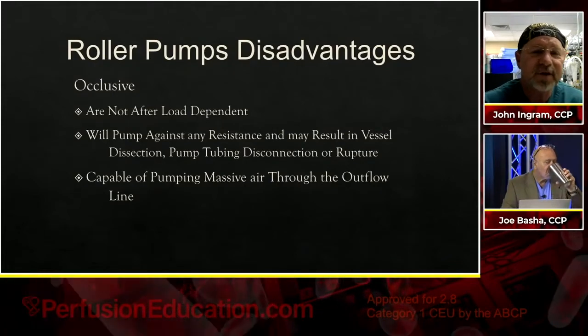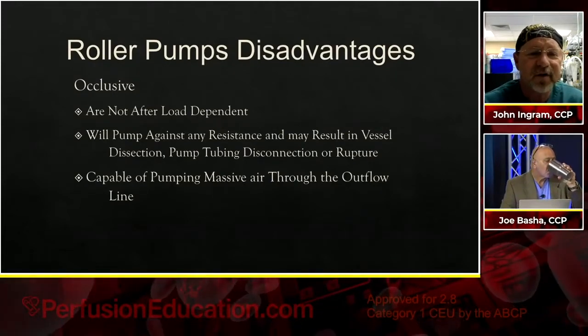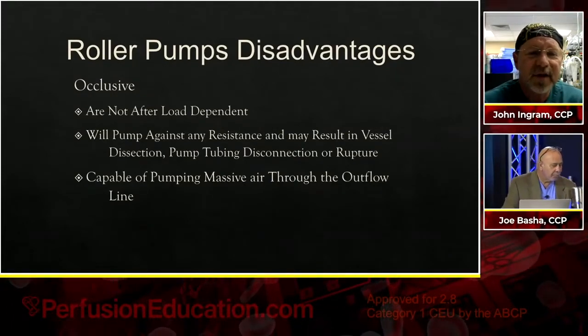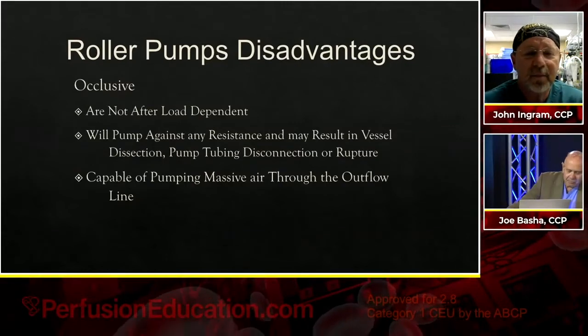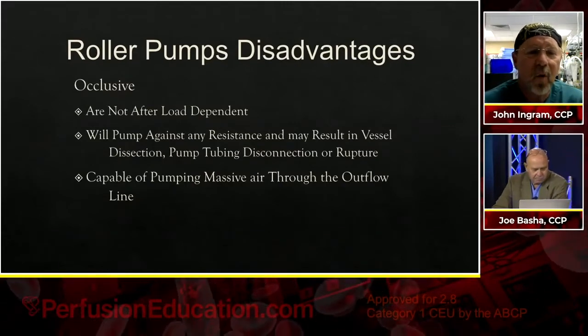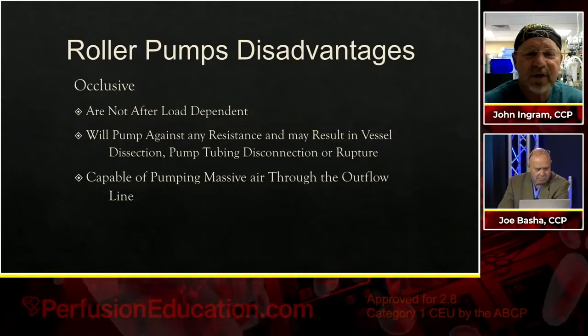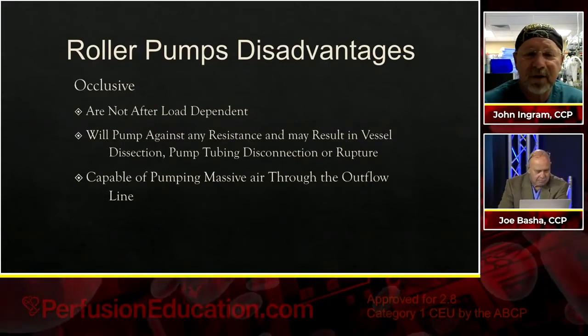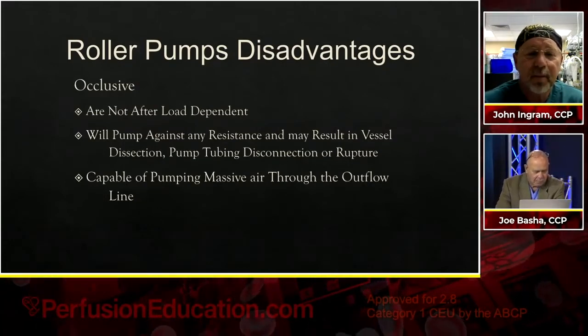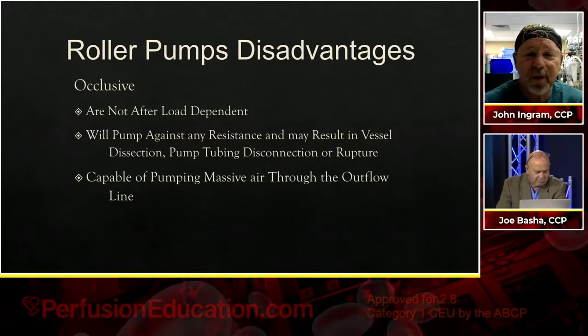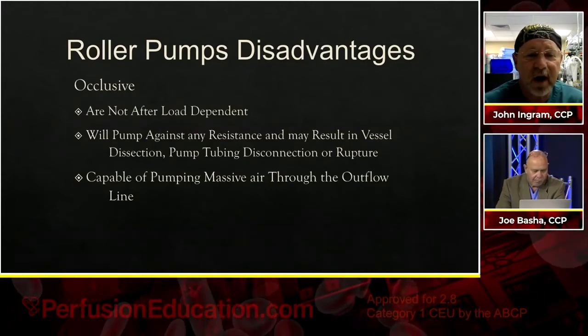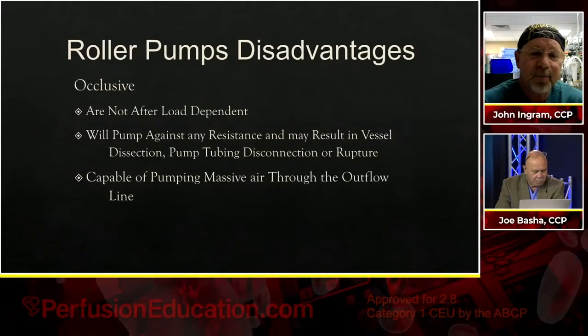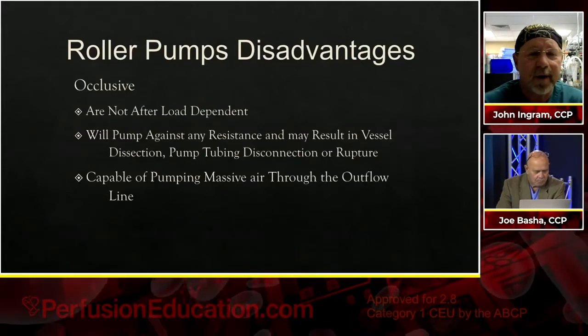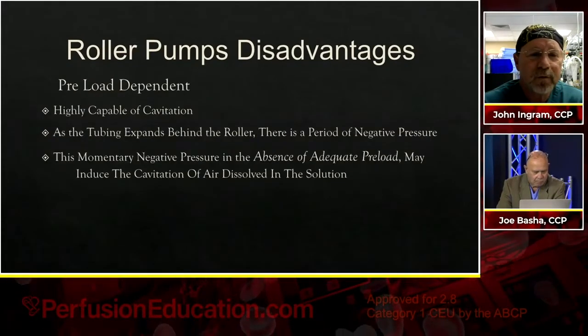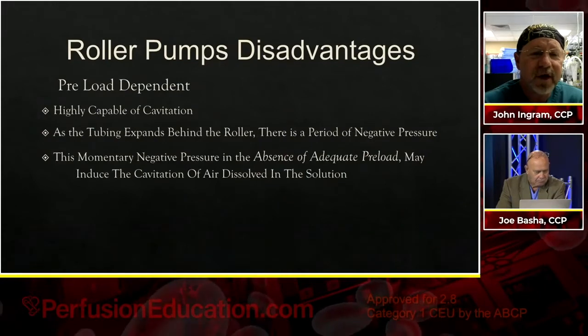The disadvantages of it are that it's an occlusive pump, and it is not afterload dependent. So it will pump against any resistance and therefore may result in vessel dissection, pump tubing disconnection, or pump tubing rupture if the pressures get high enough. It's capable of pumping massive air through the outflow line. Go ahead, Joe. That's the occlusive negative.